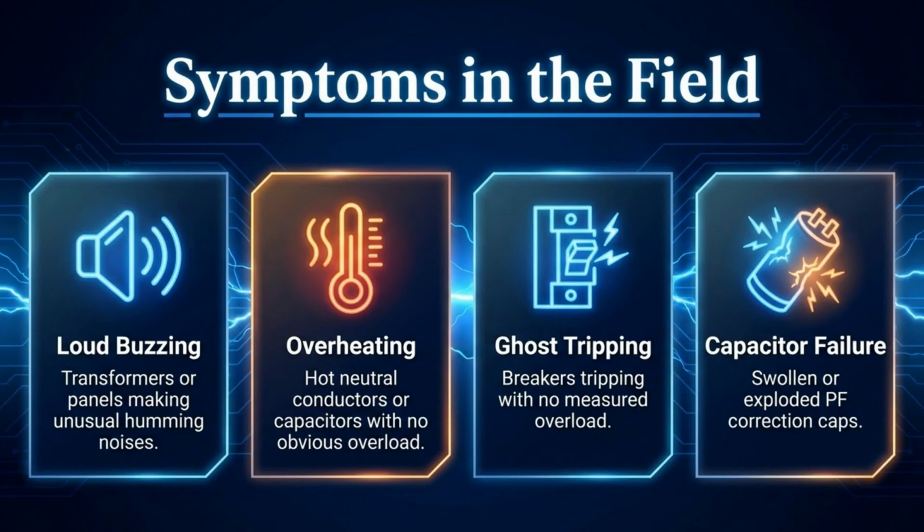Symptoms of resonance in the field include loud buzzing from transformers, overheating of conductors or capacitors, ghost tripping of breakers with no overload, and capacitor failure like swollen or exploded correction caps.